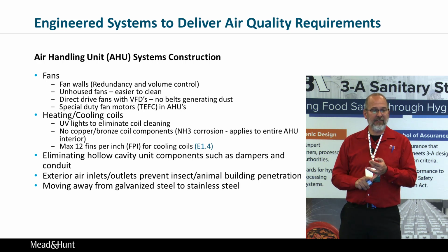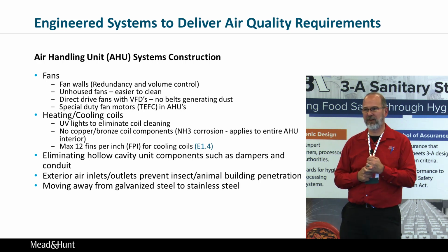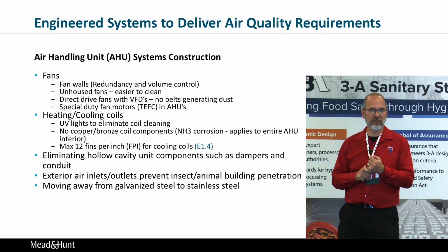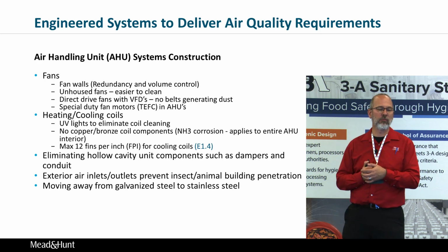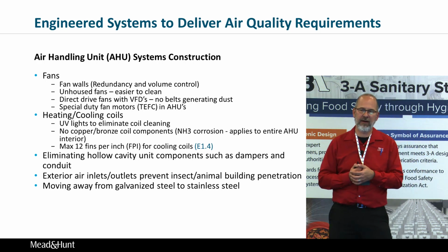The air handlers typically need to have a heating and cooling source, and that could be coils, gas heat exchangers. Again, for gas heat exchangers, stainless steel. If they're coils, I don't recommend an all stainless steel coil, tubes and fins. Very bad heat transfer. Usually it's some combination of stainless tube and aluminum fin. Avoid copper or bronze coil components, because if there's ammonia in the unit, in the coil, you'll eat through it very quickly. And we're starting to see more and more UV lights in air handling units.